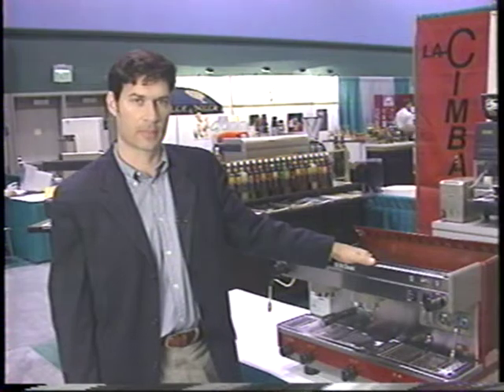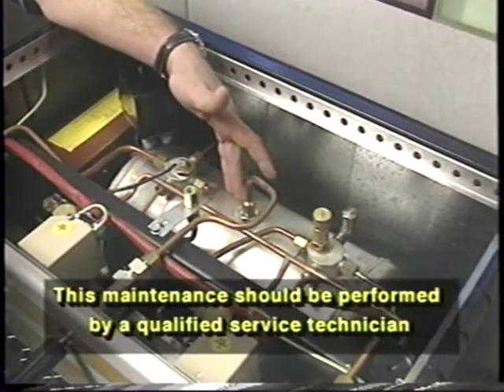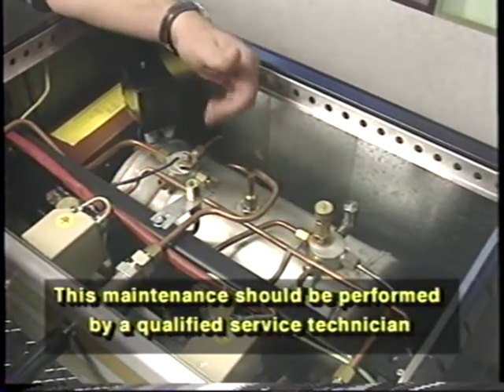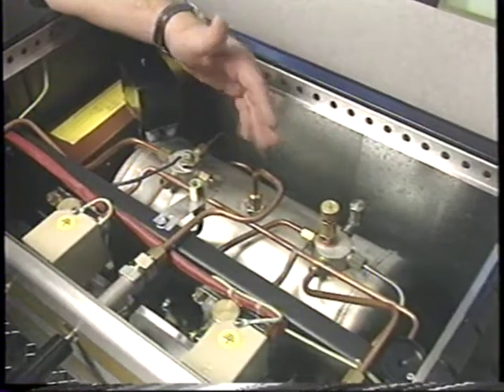So generally the 130 psi of the hot water going up inside the machine is excellent for the machine, and on a weekly basis putting the detergent up there to remove the oils out of the inside is sufficient for most bars. Other maintenance that can be performed is to drain the water from the steam boiler, and it's advisable by the manufacturer that at least annually the steam boiler is drained of its water.